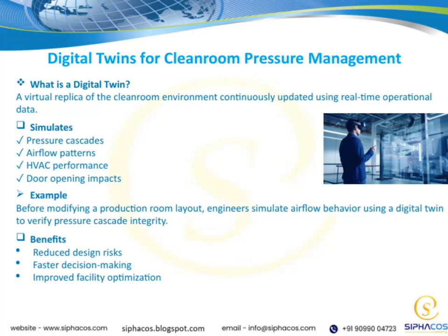Let's talk about digital twins and how they transform cleanroom pressure management. A digital twin is a virtual copy of the cleanroom, constantly updated with real-time data. It simulates key factors like pressure cascades, airflow patterns, HVAC performance, and even the effects of opening doors. For example, before changing a production room layout, engineers use the digital twin to test airflow and ensure pressure stays balanced. This approach cuts design risks, speeds up decisions, and helps optimize the entire facility.